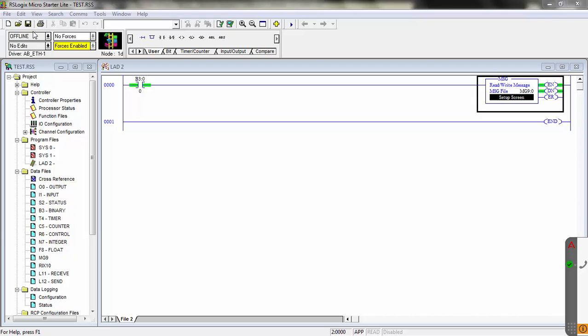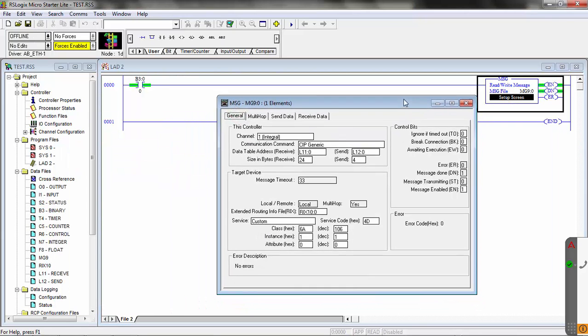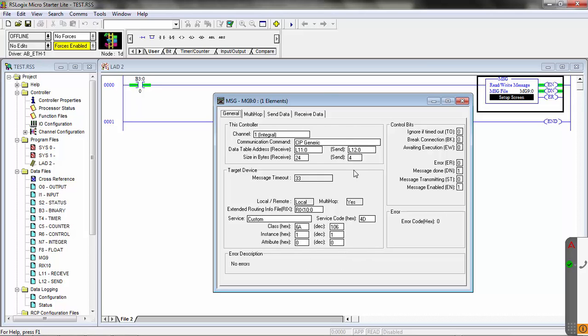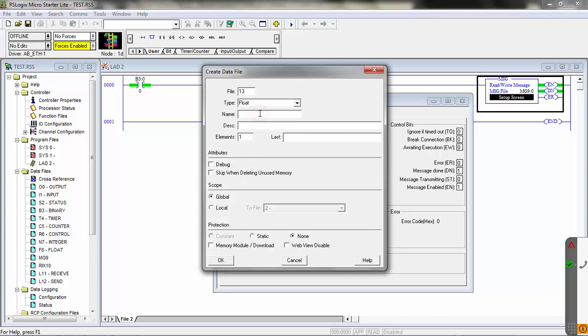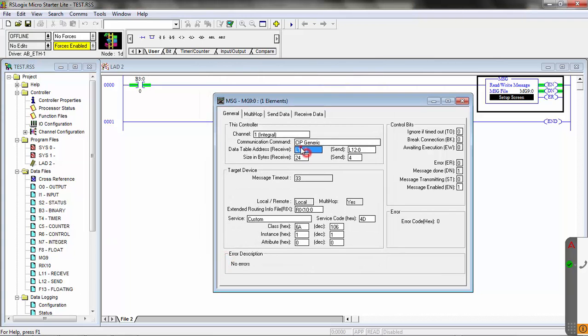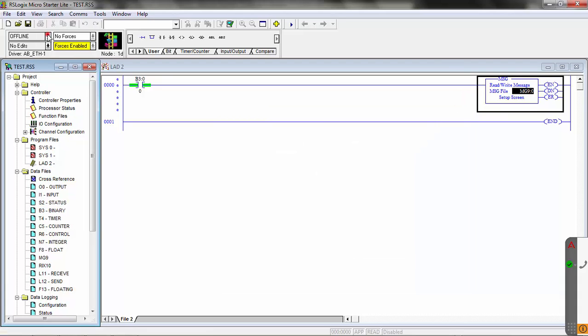Here's the PLC program again — we're offline with the PLC so we can change our message. I'll click on the setup for the message. If we're going to receive single precision floating point decimals, we need to change our receive location. We were receiving to the long type, which is a 32-bit integer, so we need to set up a floating point. On data files, we'll create a new one — we'll call it floating, with 128 elements. We need enough to make sure we have enough to receive the data. We've created our F13, so now I'll simply change this to F13 instead of L11 for our receive. Everything else stays the same — we'll receive 24 bytes, send 4 bytes, just to a floating location this time.